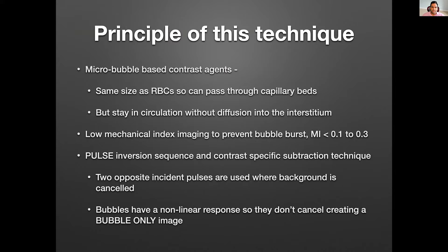The principle of this technique is that these agents are microbubble-based contrast agents. They're the same size as red blood cells, so they can pass through capillary beds, but they stay in the circulation without diffusing into the interstitium. You do need to use a low mechanical index imaging to prevent bubble burst, so the MI needs to be less than 0.1 to 0.3. You use a pulse inversion sequence and a contrast-specific subtraction technique, so your ultrasound machine software needs to be upgraded to have these two sequences.